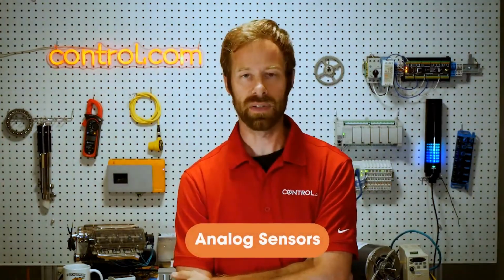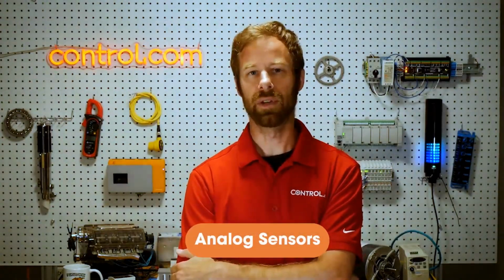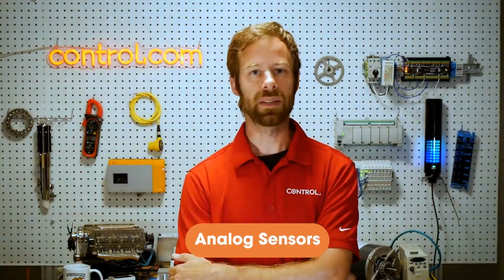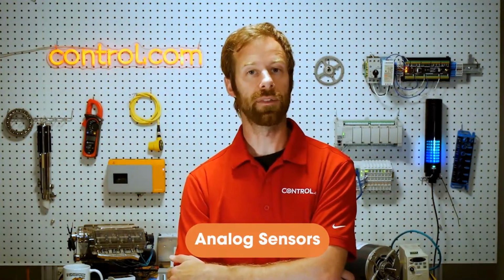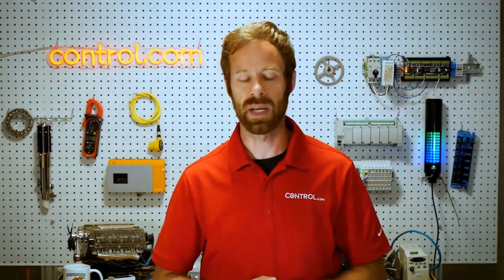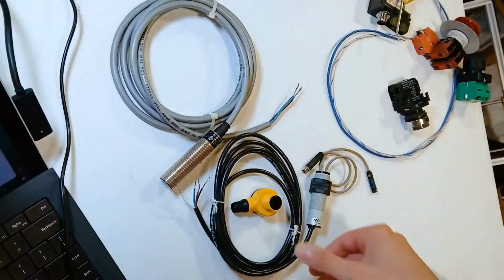One other that's worth mentioning here, mostly because it's very similar to the digital 3-wire sensors, is analog sensors, sort of the complement of digital. Analog means that instead of providing that on-off threshold, we're providing a whole range of voltages or currents. 4 to 20 milliamps is very common. Also 0 to 10 volts is very common, but there's exceptions to that. That provides an entire range between a minimum and a maximum of sensing distance.